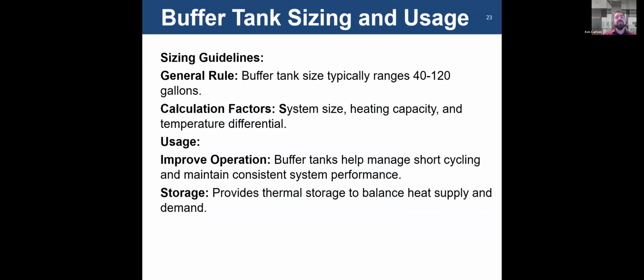Biggest thing being the buffer tank, as it's quite sizable. Generally, buffer tanks are in the range of 40 to 120 gallons, depending on the size. There's some different industry terms out there; 20 gallons a ton is a number that's thrown around a lot. The manufacturer will oftentimes help you calculate the buffer tank size that you need to make sure that it's sized appropriately. Depending on the heating capacity, temperature of the system, and what you're actually serving in the system, it will change how big that tank needs to be. So make sure it's sized appropriately. Those don't go by rules of thumb.